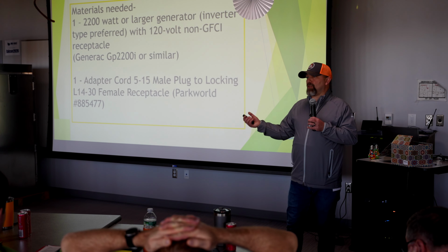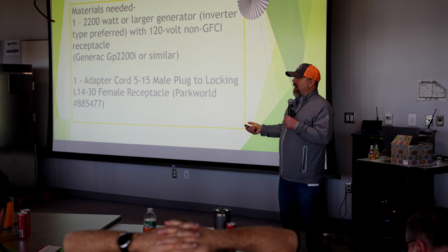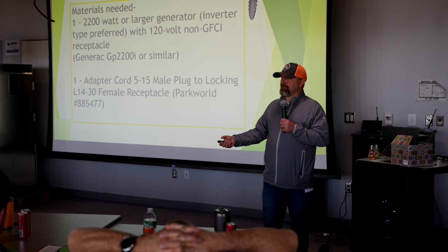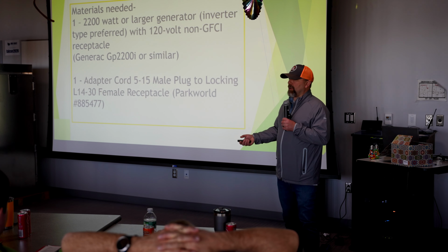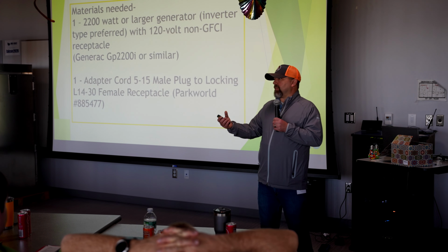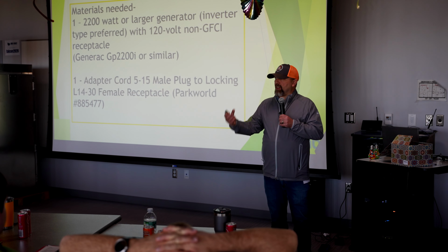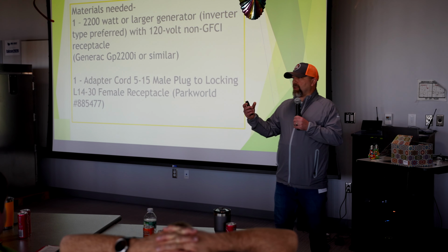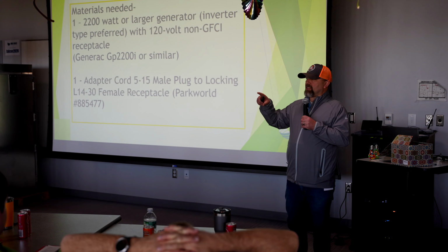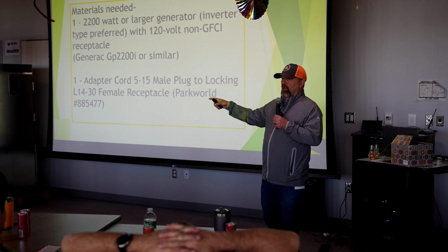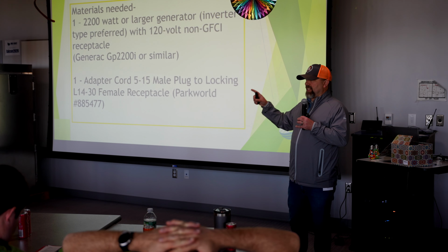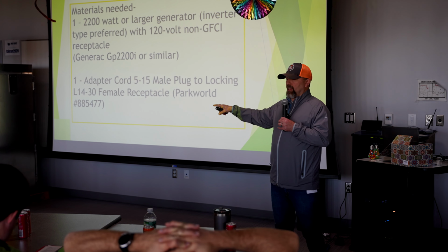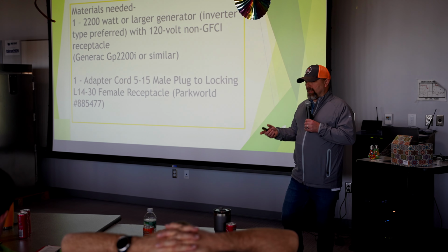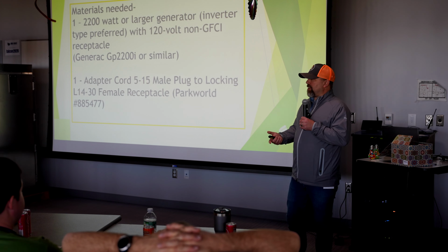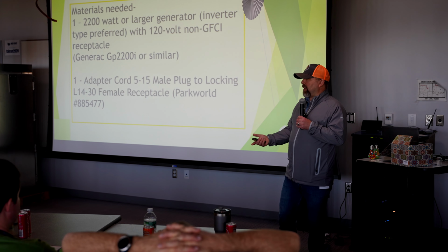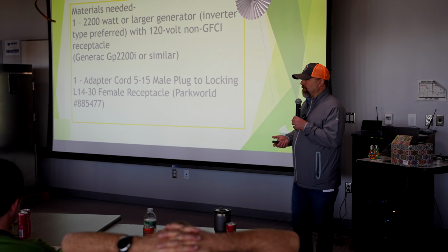So there are two lines of thinking. If you're going to put it on generator power, you can either use a small suitcase generator, an inverter type being preferred for cleaner power out of it. Then you can use an adapter cord that takes the standard 110 plug off the generator and brings it to a 4-wire plug. What that adapter cable does is bridge the two hot legs together, because you don't know which leg they wired to in the transfer switch. So it supplies power to both of them, and you'll power the correct leg in the cabinet. The other option would be to bring out a larger generator that has a 240 volt 4-wire plug on it and just hook it up, and it's one-for-one at that point.